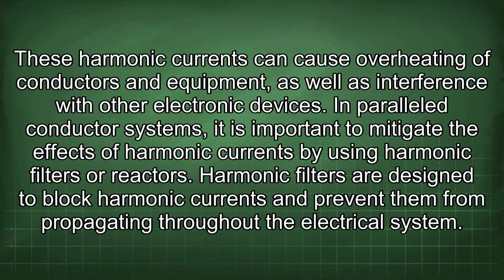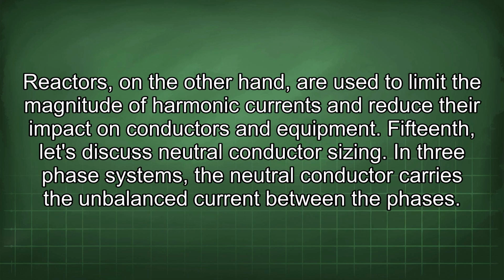Harmonic filters are designed to block harmonic currents and prevent them from propagating throughout the electrical system. Reactors, on the other hand, are used to limit the magnitude of harmonic currents and reduce their impact on conductors and equipment. 15th, let's discuss neutral conductor sizing.